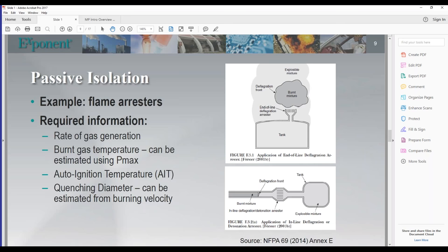Basically, you have a combustible gas going through the arrestor, and you want to prevent the flame from entering the enclosure. The second one is the in-line deflagration arrestor, where you have a combustible mixture that is burning and it's going to reach the flame arrestor, and you want to quench the flame so that you don't have flame shooting out of your system.